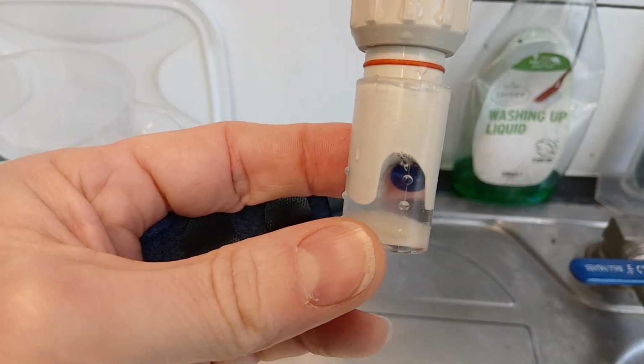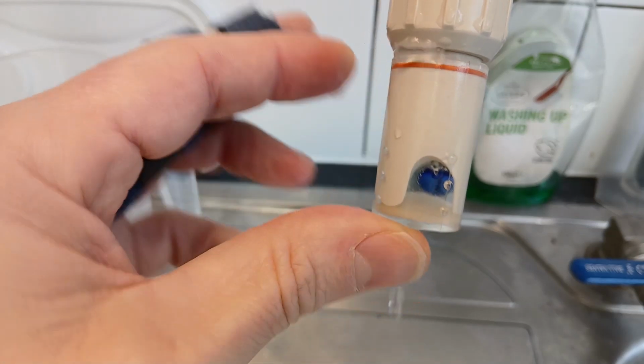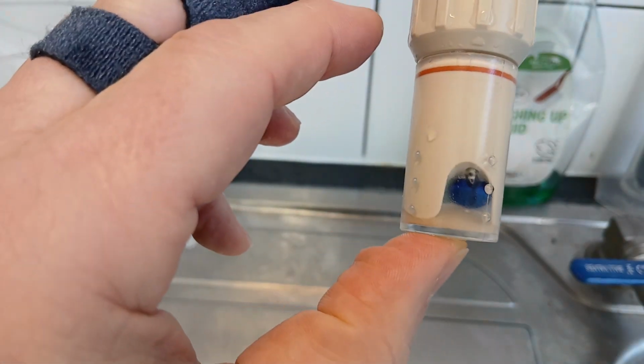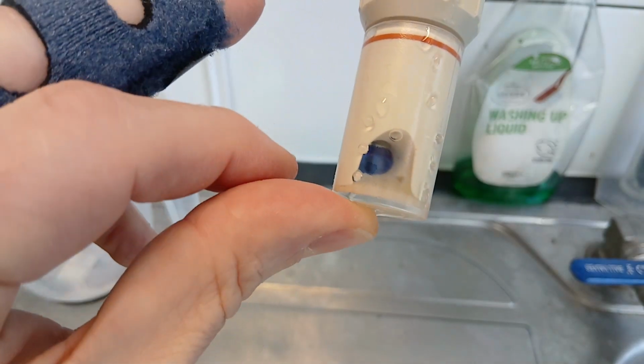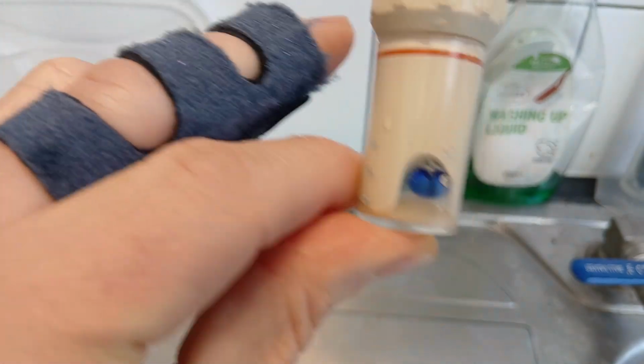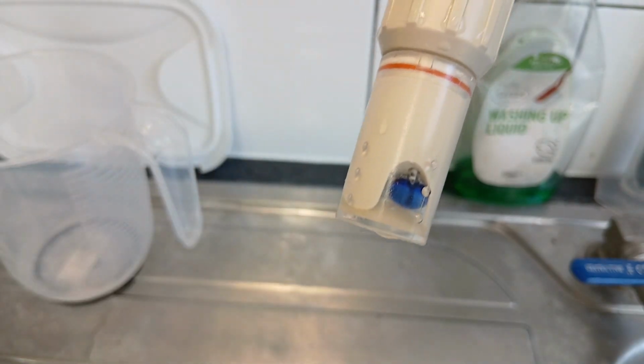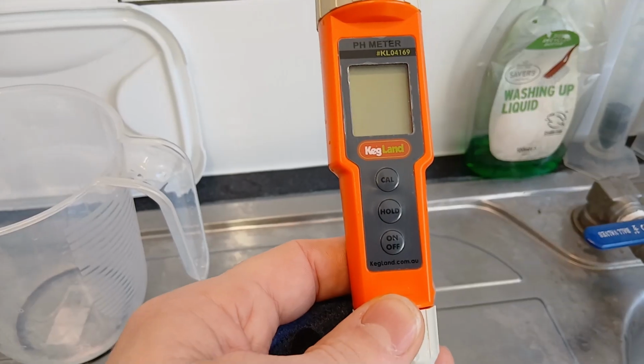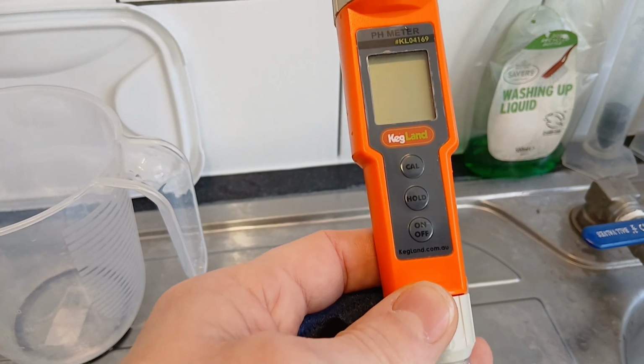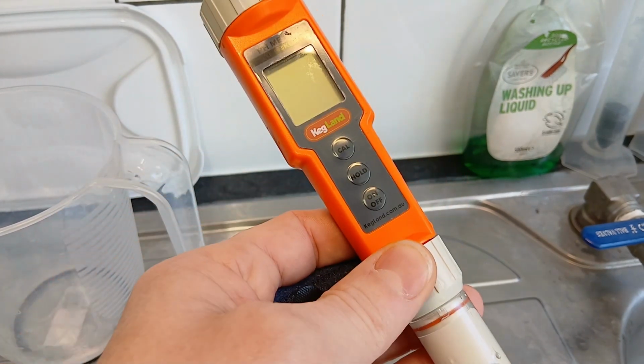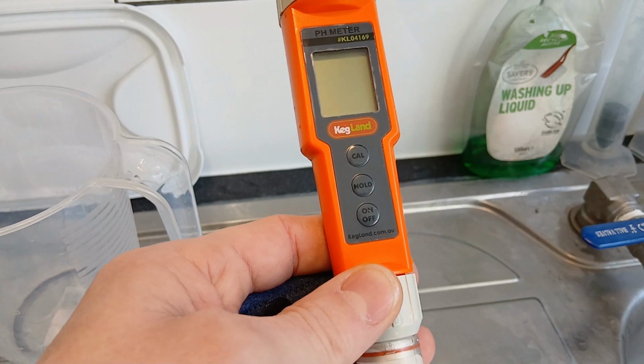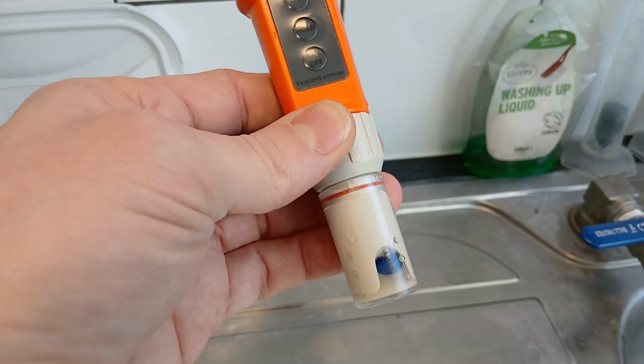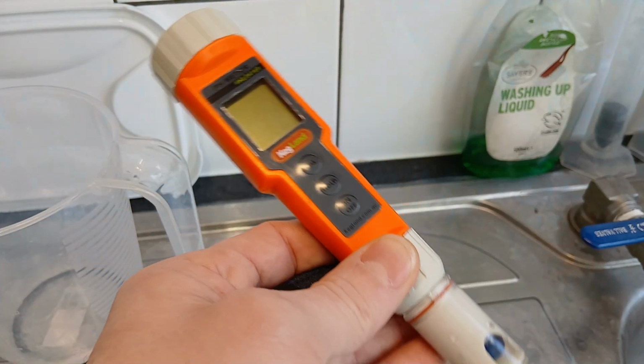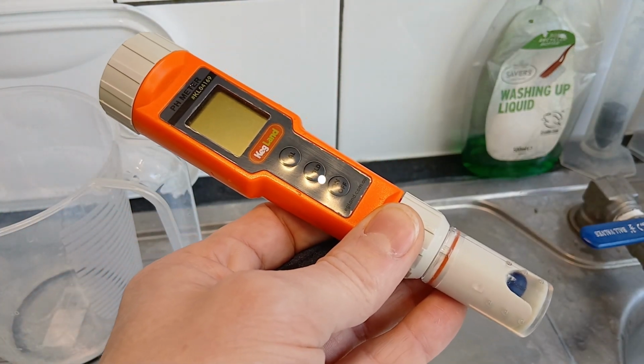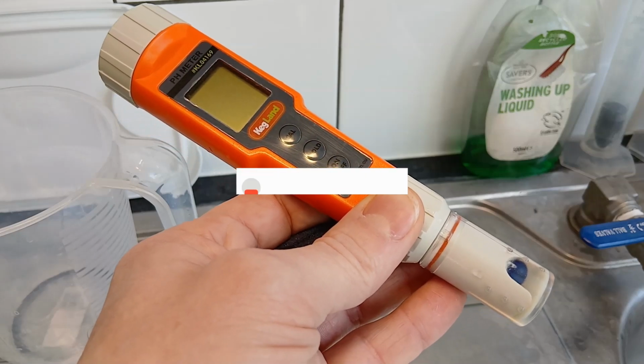I just want to make sure that electrode is fully immersed for storage. No air bubbles in there. Tiny little one there at the top there, but that's not going to bother us. So that's now safe to store and use next time we're brewing. So that was how I look after, maintain, clean and calibrate my pH meter. As I said, you can see from the results, all pretty happy with the results we got. Now I'm just going to store it away, ready for the next brew.